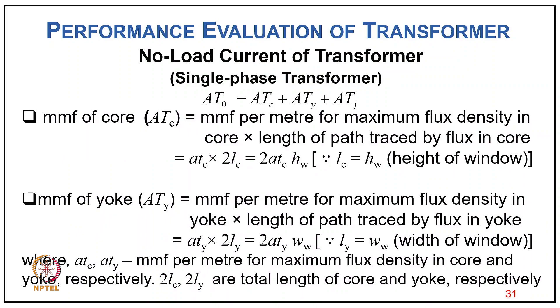The MMF for the core ATc = atc × 2Lc = 2×atc×hw, where Lc = hw is the height of the window/limb. The MMF required for the yoke ATy = aty × 2Ly = 2×aty×ww, where Ly = width of the window. Here atc and aty are the ampere-turns per meter for maximum flux density in the core and yoke respectively, and 2Lc and 2Ly are the total lengths of core and yoke.